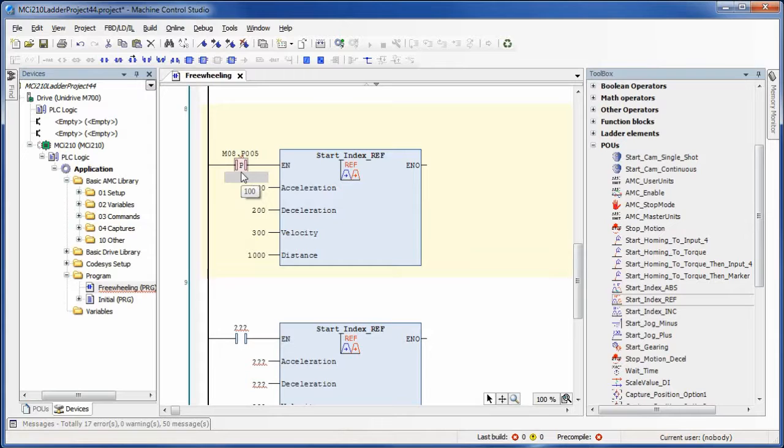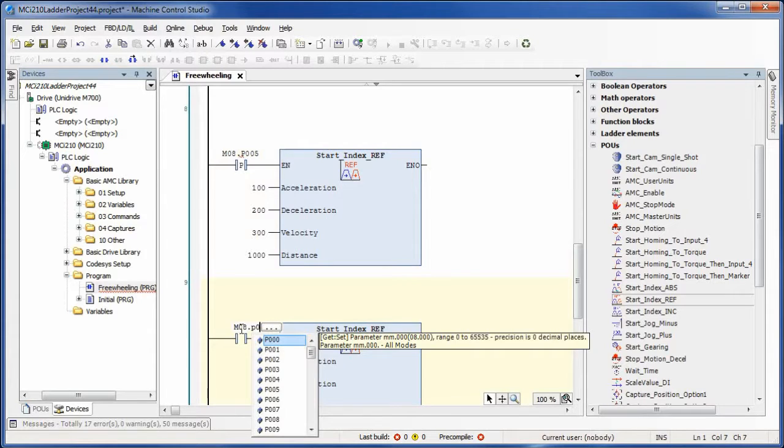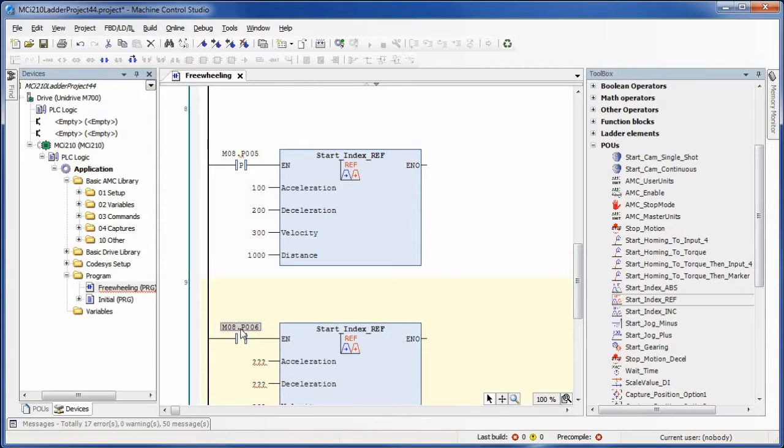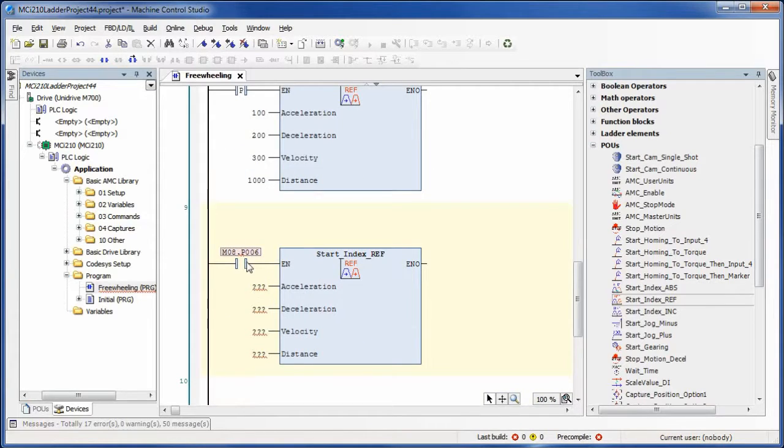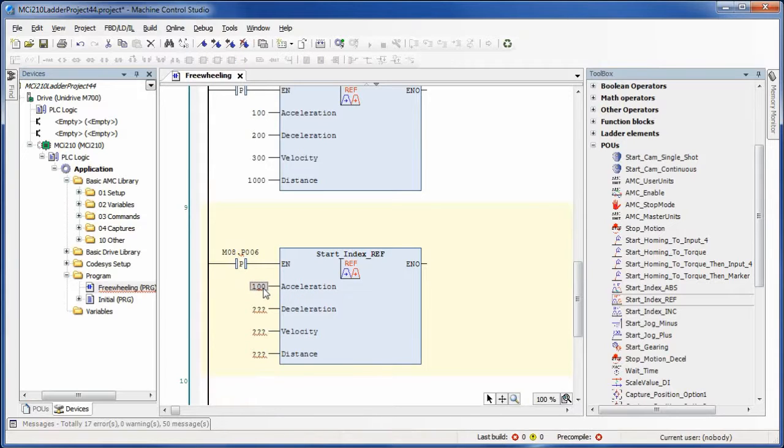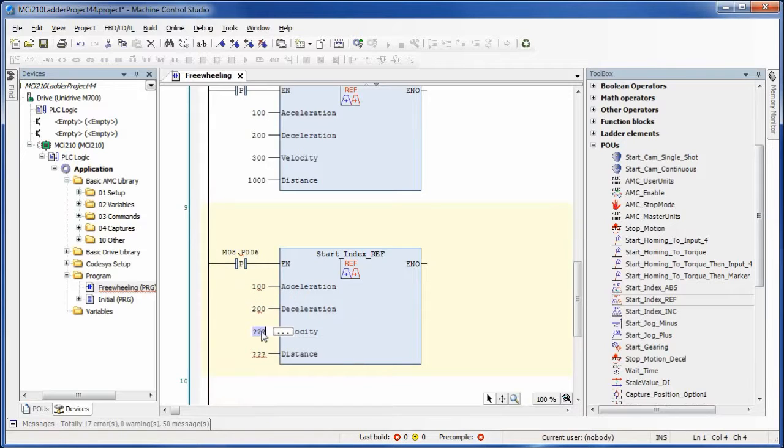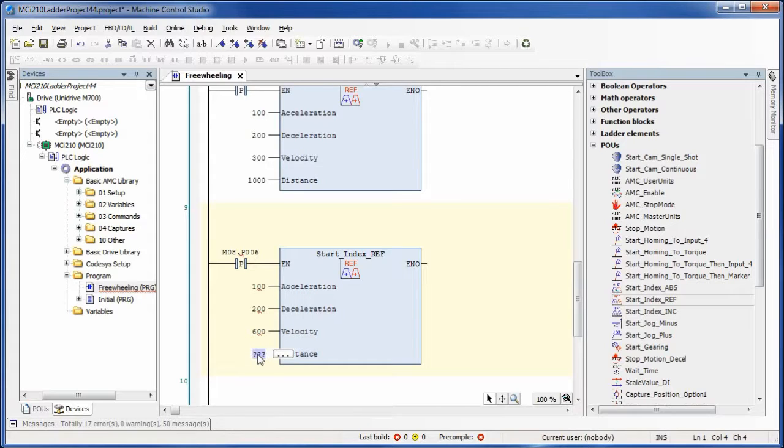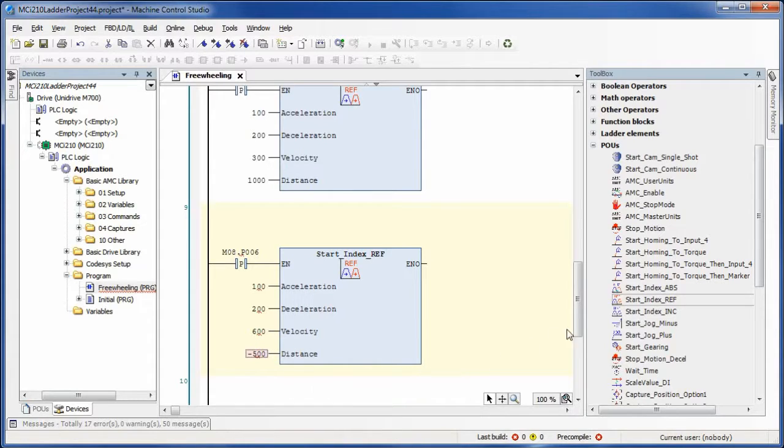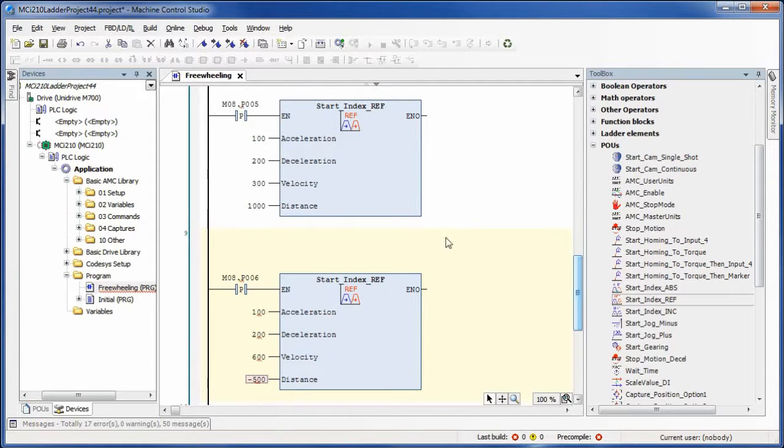I would use positive edge contacts anytime I'm dealing with start index reference. This is because this particular function will command a new index based on the last reference every time this block runs. Let's say we wrote this code without any positive edge contacts and our start index reference based on the scan time actually executed three times before we opened up the contact. If the distance was a value of 1000 like we have here, the resulting index would actually be 3000 because it would add the three indexes together.